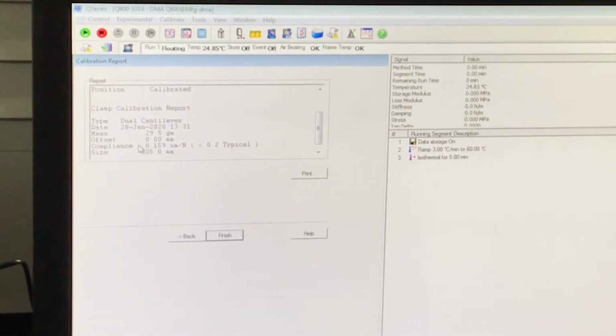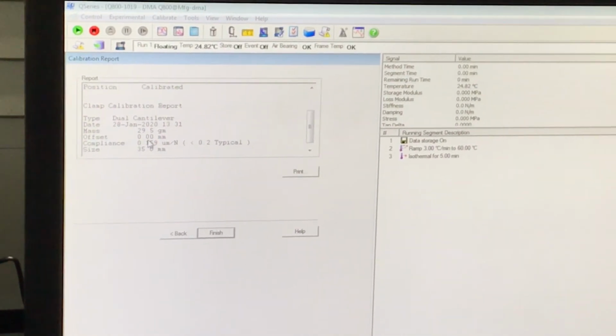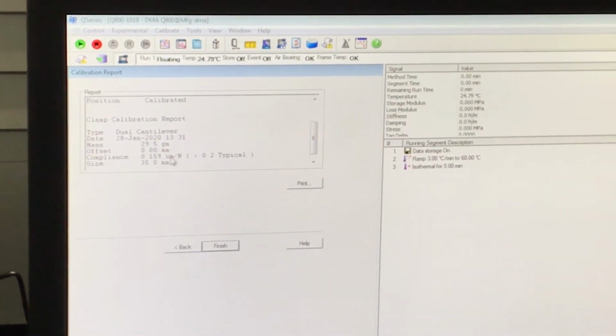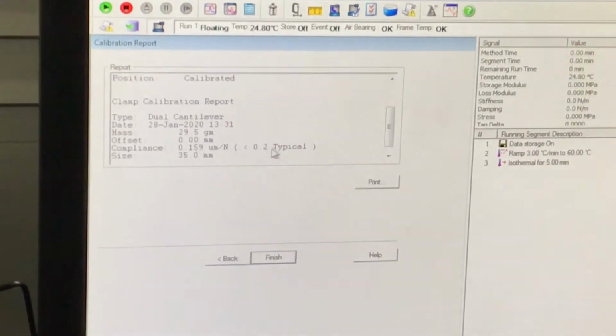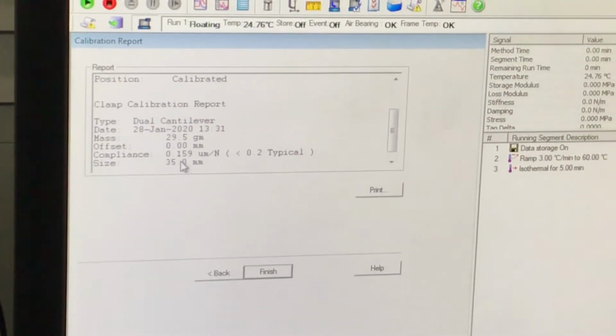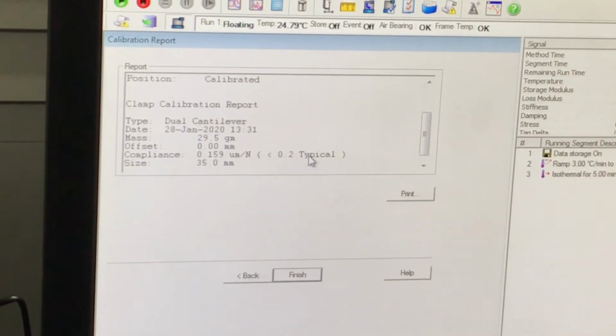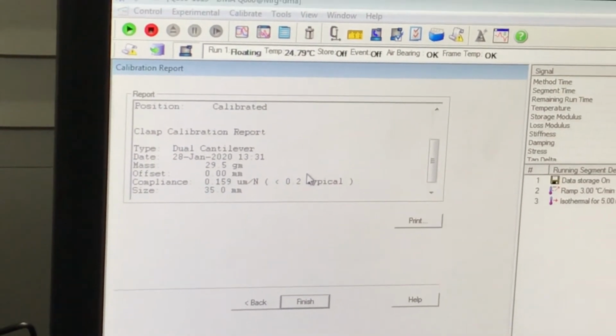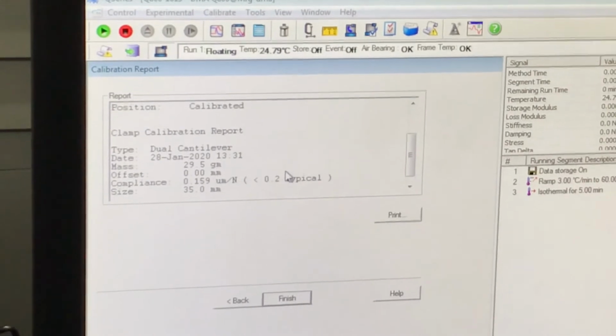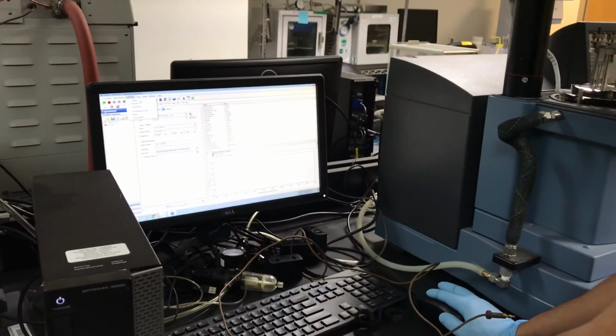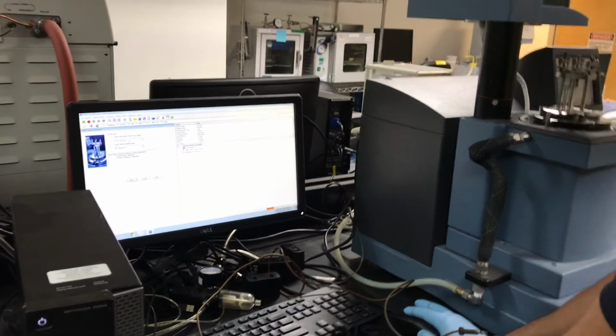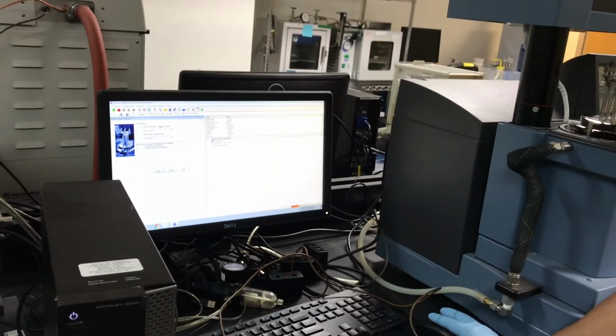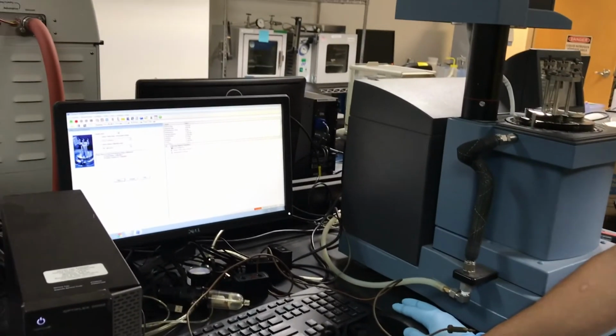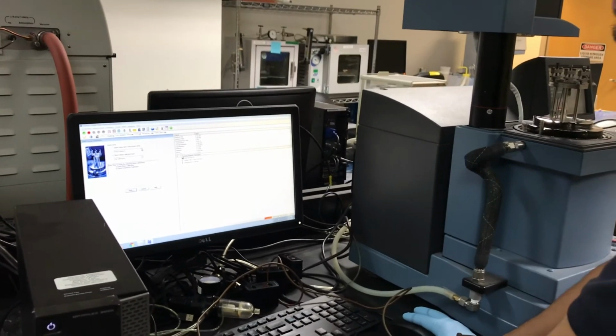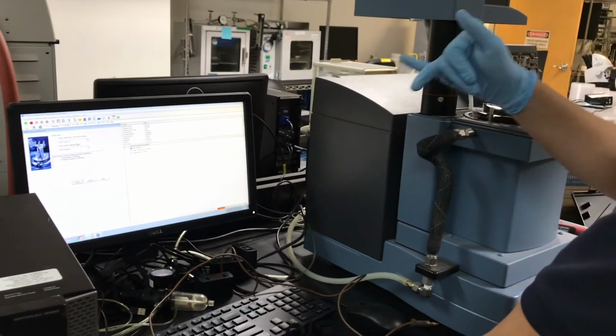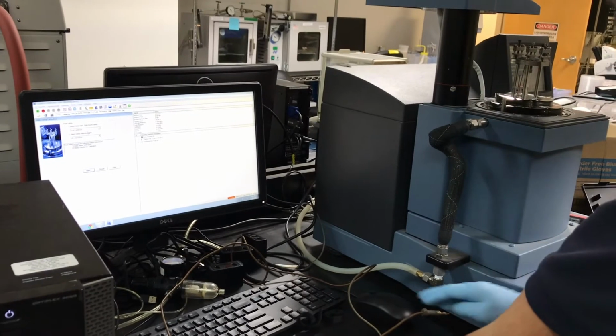Okay, so this is what you want to look for right here. You want to look at the compliance, and you want the compliance to be less than the typical value. So this is reading 0.159, and the typical is 0.2. So calibration passed, we're good to go. We just did that one clamp calibration, so for the dual cantilever, the compliance came back good to go. We're well within the range that we're supposed to be for that size of standard and for this dual cantilever clamp.